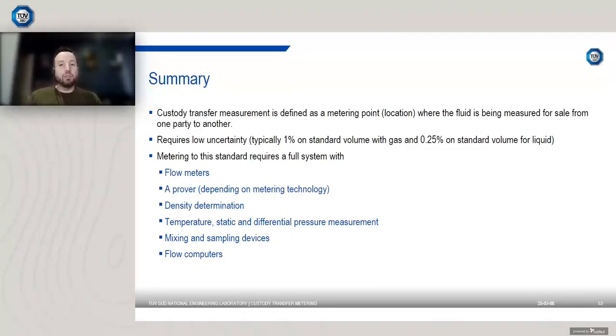So we've come to the end. Just a quick summary. Custody transfer metering is defined as a metering point where the fluid is being measured for sale. So it's acting as the cash register. It requires a low uncertainty, typically 1% on gas and 0.25% with liquid. And to meter to this uncertainty, you require a full, comprehensive system that includes flow meters, provers, density, temperature, pressure, sampling, and flow computers as well.